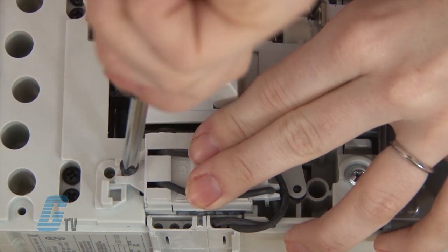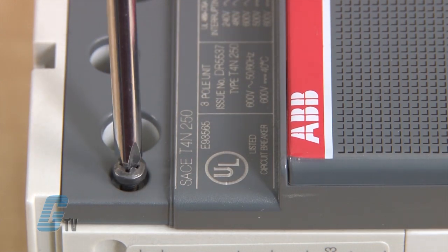I will use the larger M4 by 12 mounting screw for fastening the top of the UVR to the breaker, and I will use the M3 by 10 mounting screw for the bottom. Now I will reinstall the front cover and fasten the screws to the frame.